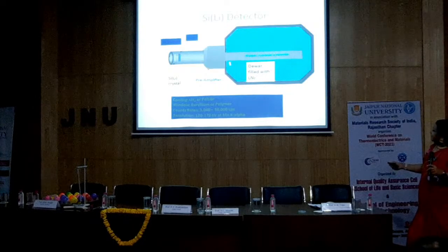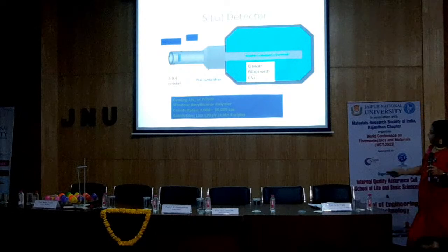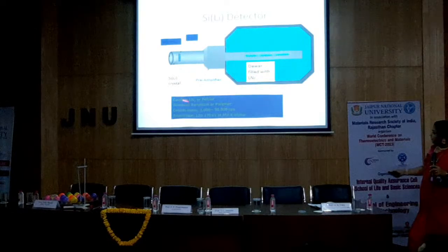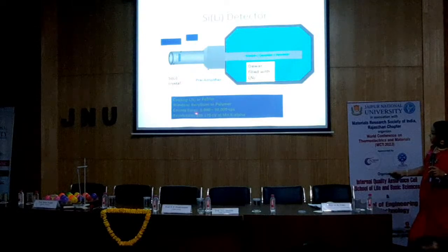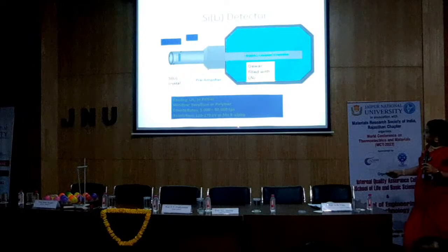So here you see what it is. It is a crystal basically. Here you have the preamp, the dewar which has liquid nitrogen, and you have the detector. The window is beryllium or polymer, and of course you have to fill the liquid nitrogen, and the counts are around 3000 to 30,000 CPS.